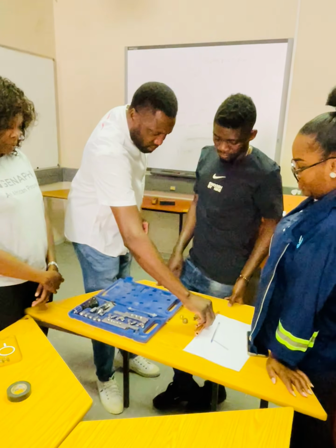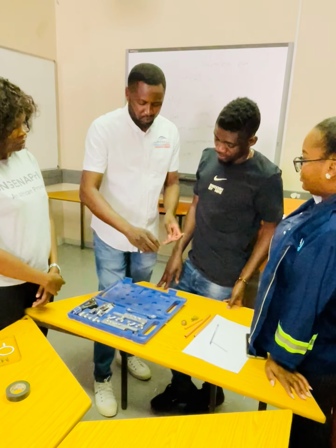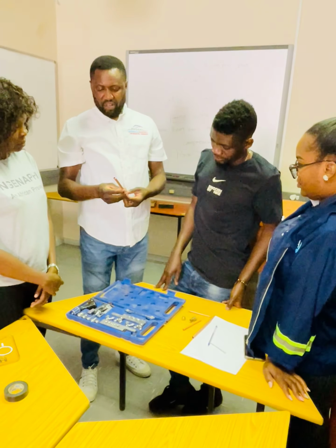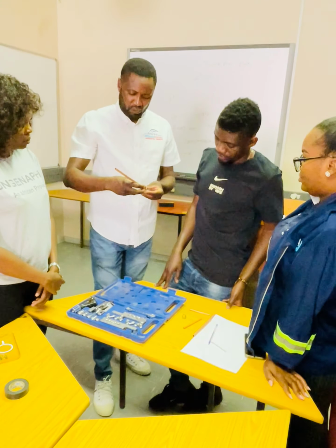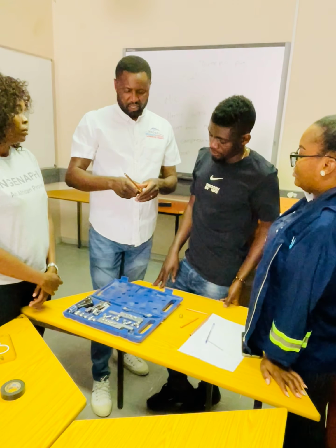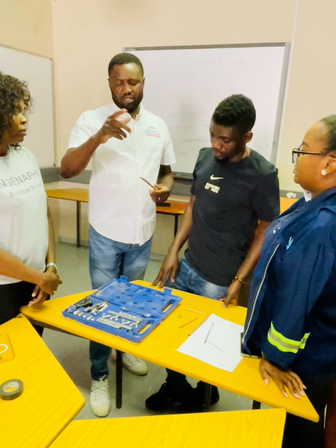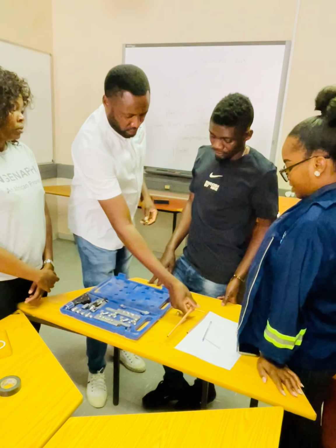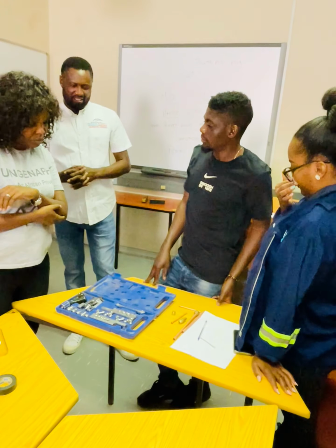And let's go back a little bit to the flaring. With flaring, we should be able to put on a nut. Let's demonstrate with this one for the 3/8. After you flare it, you put on your nut. Then you should be able to connect to your valve, to your AC valve or your fridge's valve. Then from here you can extend it by swaging it, then extend to another unit. Good. Any questions so far? No, sir.